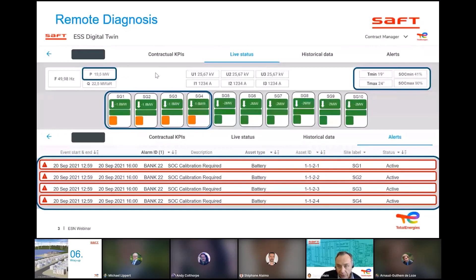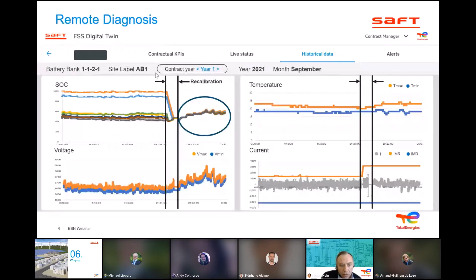So Saft worked with our customer to establish a 15-minute break of the battery systems requiring this recalibration. And during this time, the system ran a self state of charge calibration routine that allowed the strings to achieve the desired state of charge, as can be seen in the trend here. So at this point, the state of charge calibration alarm was resolved.